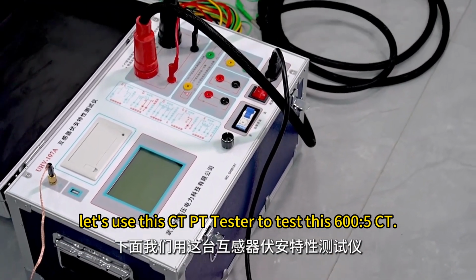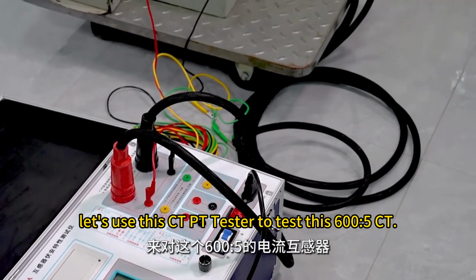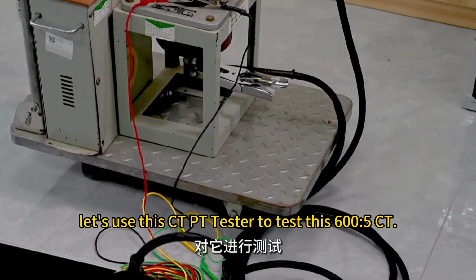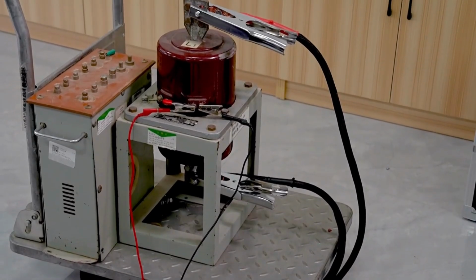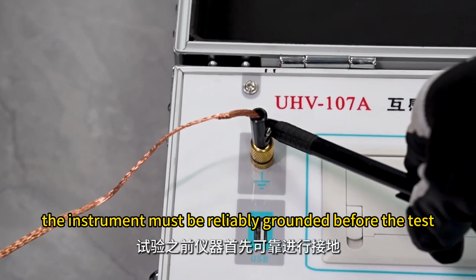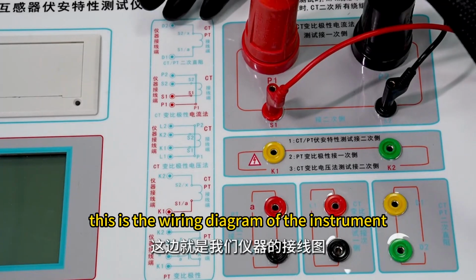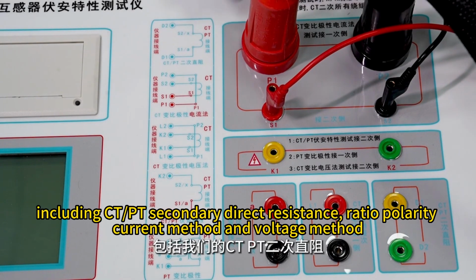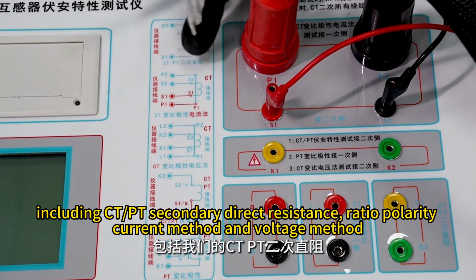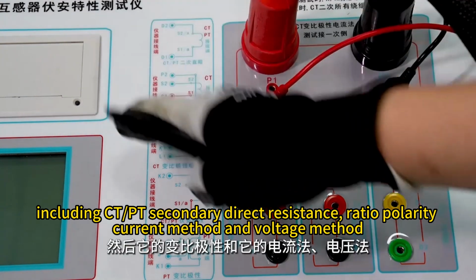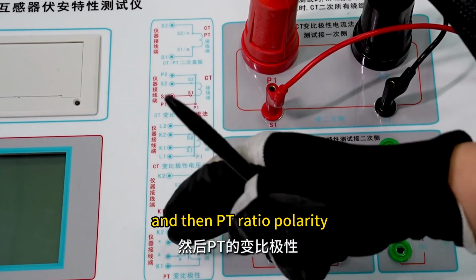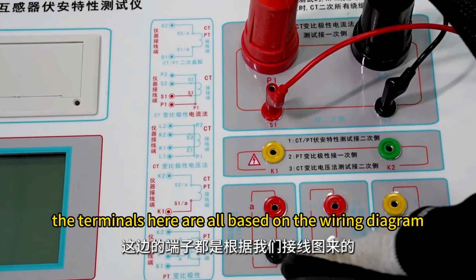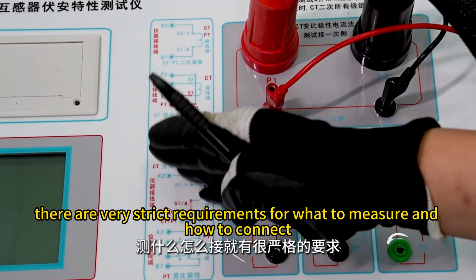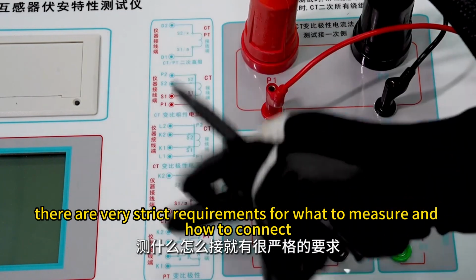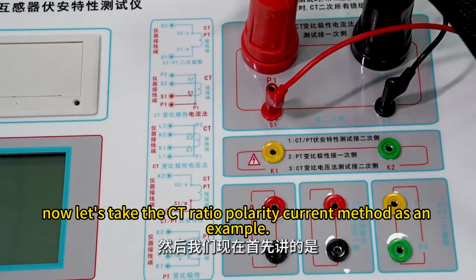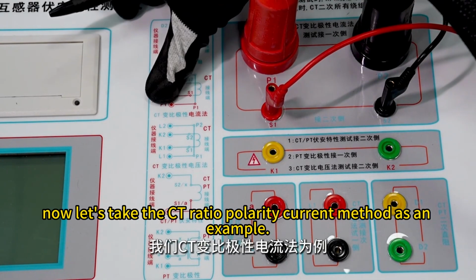Let's use this CT PT tester to test this 600:5 CT. The instrument must be reliably grounded before the test. This is the wiring diagram of the instrument, including CT-PT secondary direct resistance, ratio polarity current method and voltage method, volt-ampere characteristics, and then PT ratio polarity. The terminals here are all based on the wiring diagram. There are very strict requirements for what to measure and how to connect. Don't connect it wrong. Now let's take the CT ratio polarity current method as an example.